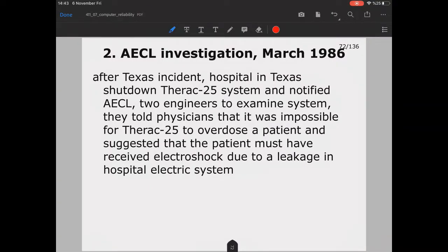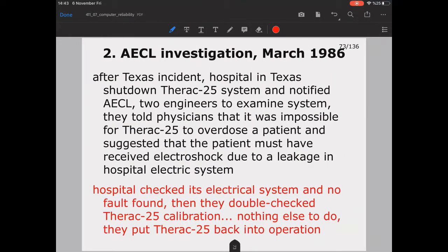After the Texas incident, the hospital shut down its Therac-25 system and notified the AECL. Two engineers were sent to examine the system. They told the physicians that it was impossible for the Therac-25 to overdose a patient, and suggested that the patient must have received an electroshock due to a leakage in the hospital electric system. The hospital checked its electrical system and no faults were found. Then they double-checked the Therac-25 calibration again. They found nothing, and had nothing else to do. They put the Therac-25 back into operation again.